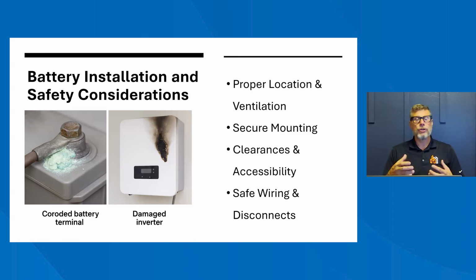The next thing is we want to make sure it's securely mounted to the wall or whatever it's supposed to be secured to. It has to be secure, you don't want that thing falling over, it is heavy, especially if it's like a Tesla Powerwall, which is becoming more common now. Make sure it's firmly attached, there are no gaps in it, and that there's enough space for airflow around it and for the tech to get to it. The way it's attached to the wall is typically a big concern.